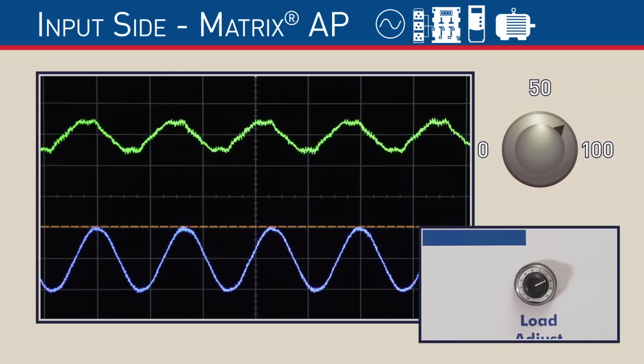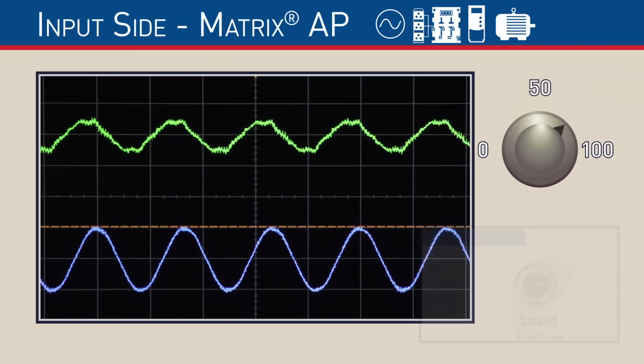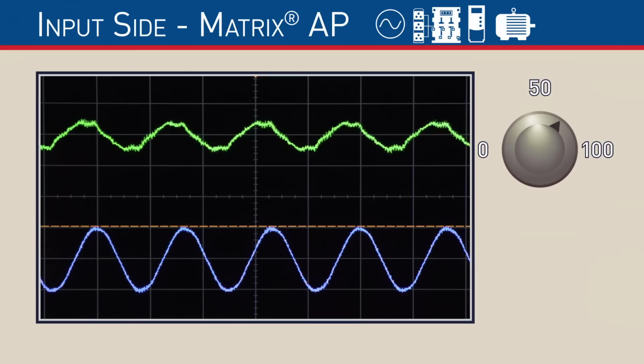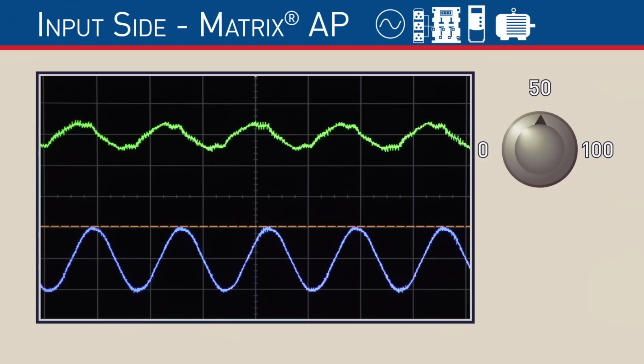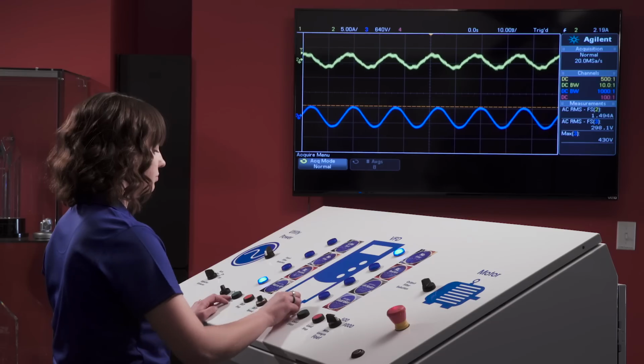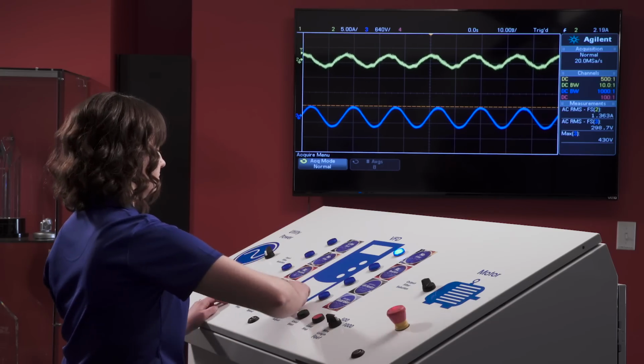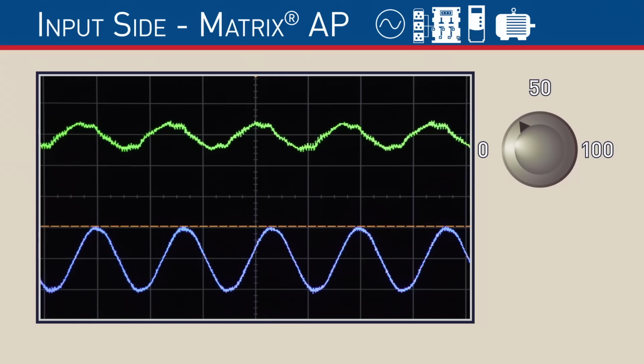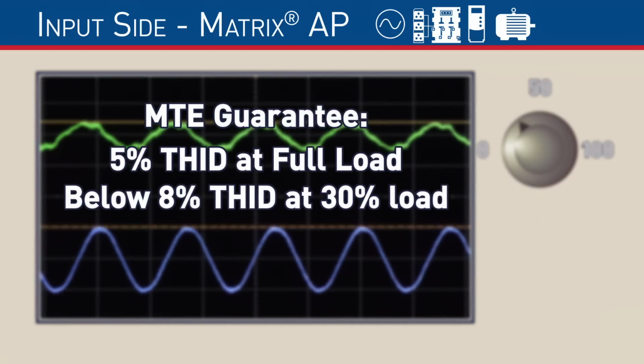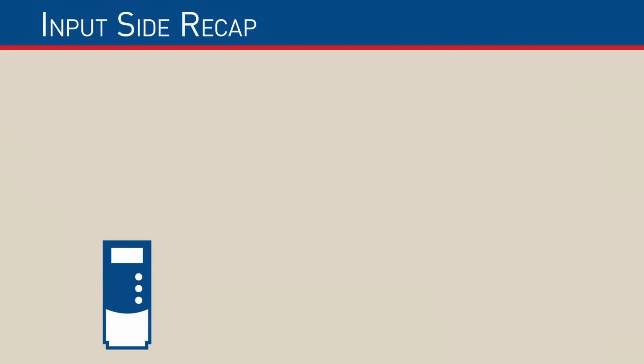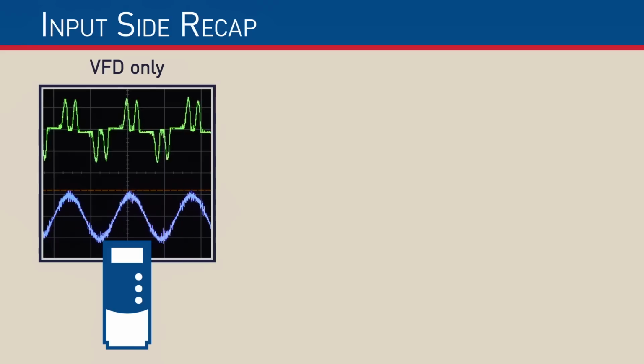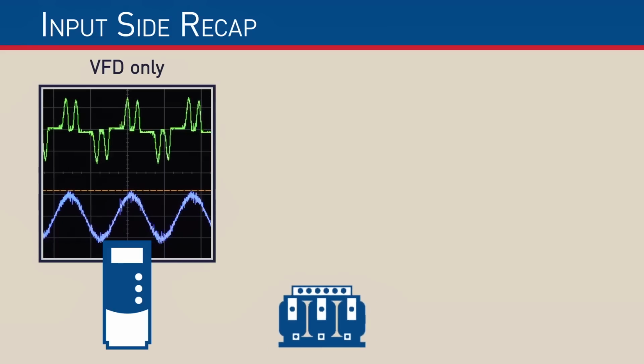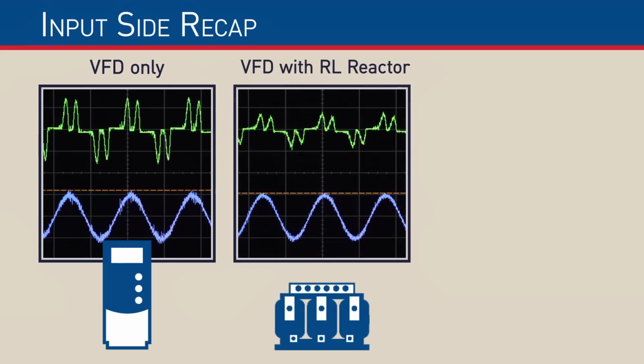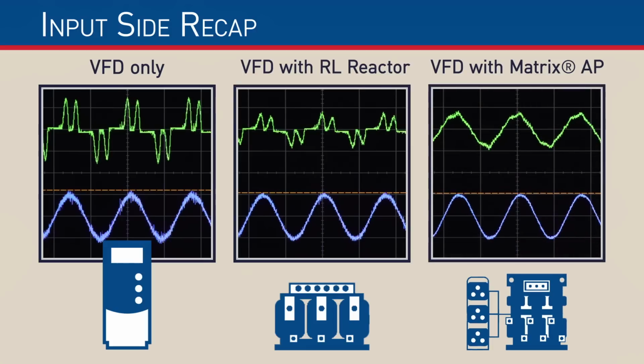As we decrease the load to about 75%, you can see that the current waveform is nearly unchanged. In reality, we typically see a 5% harmonic level with the Matrix AP down to a load of 50% or less. Even as the load reaches 30%, we are still showing a relatively strong current waveform. MTE actually guarantees an 8% current distortion level to a 30% load. Let's recap the differences in harmonic distortion for the VFD without protection, the VFD with an RL line reactor, and the VFD with a Matrix AP harmonic filter.